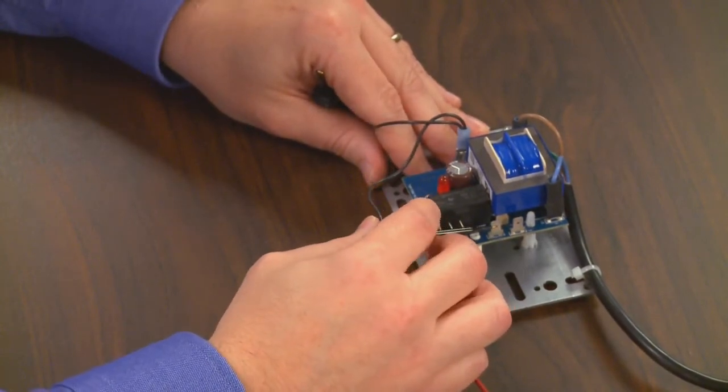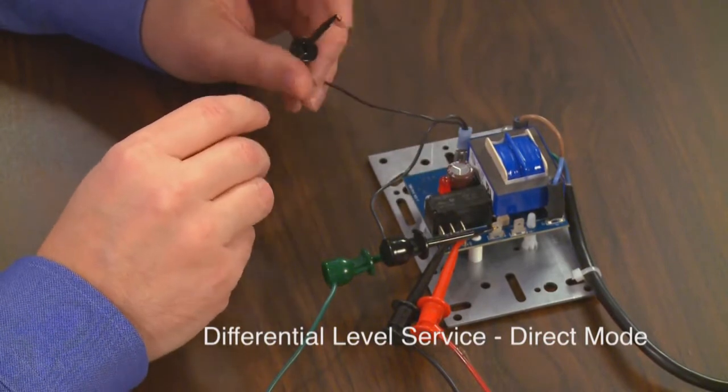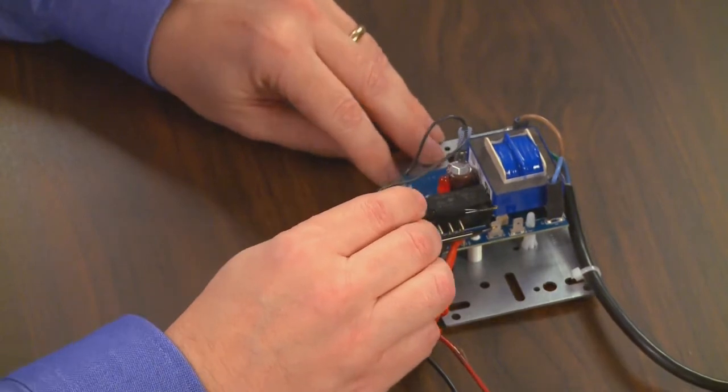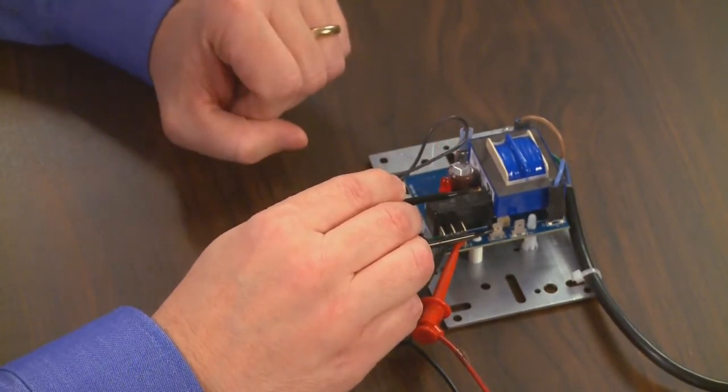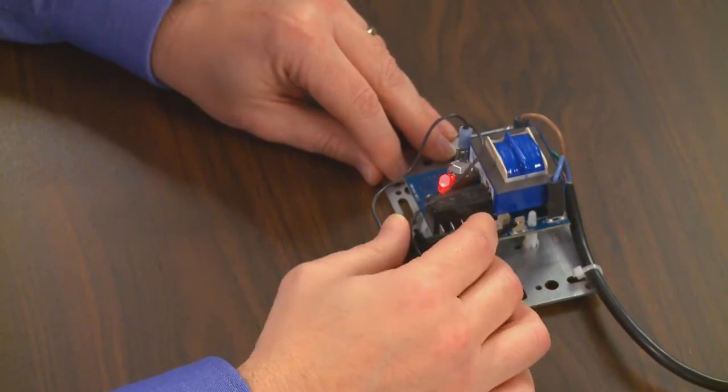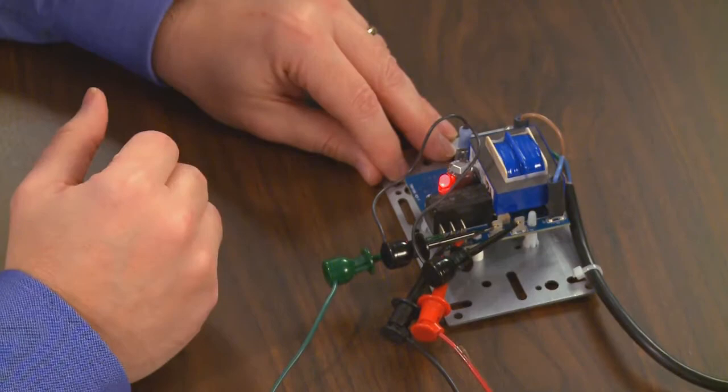As you see the LED remains off meaning the relay is in its shelf state or de-energized state. As the water rises to the high probe simulated by our jumper from the reference point to our high probe connection you notice the LED turns on the relay is now energized.